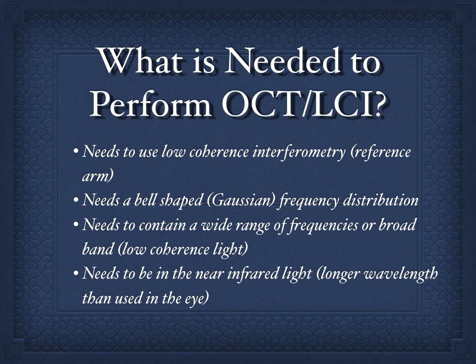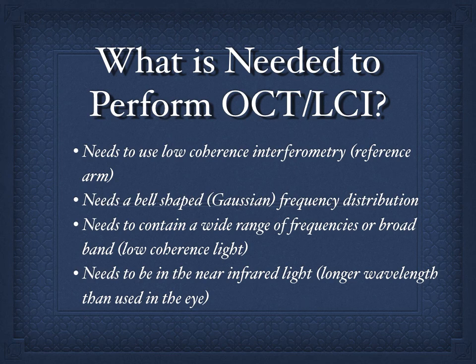What is needed to perform OCT or LCI? They're both based on low-coherence interferometry. OCT is just two-dimensional LCI or three-dimensional LCI. You need a reference arm, you need a source with a Gaussian or bell-shaped frequency distribution, and this is critical. You want broadband. It needs to contain a wide range of frequencies or wavelengths, which makes it low-coherent light. And it needs to be in the infrared.